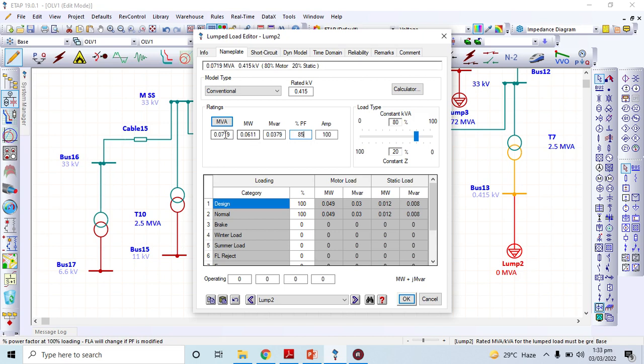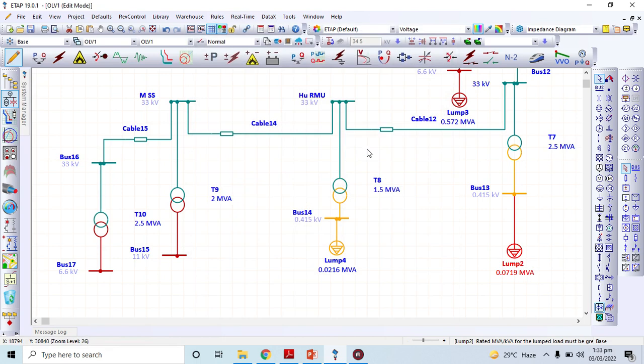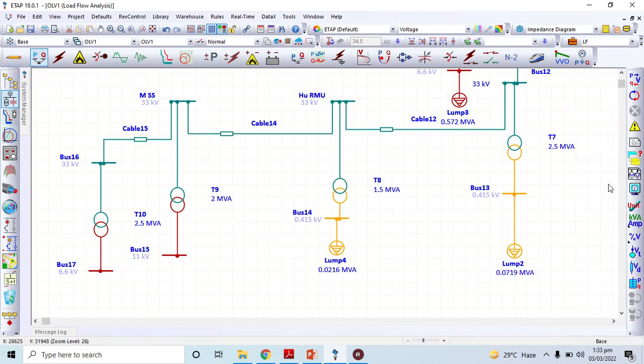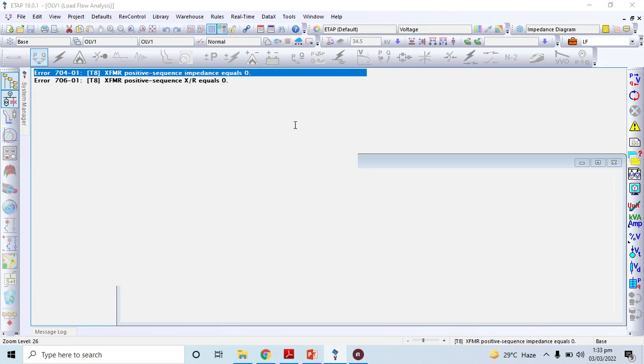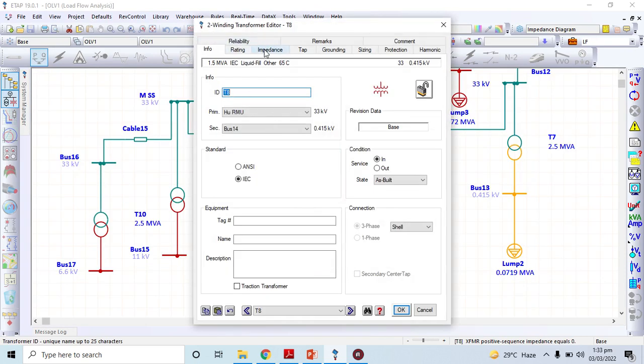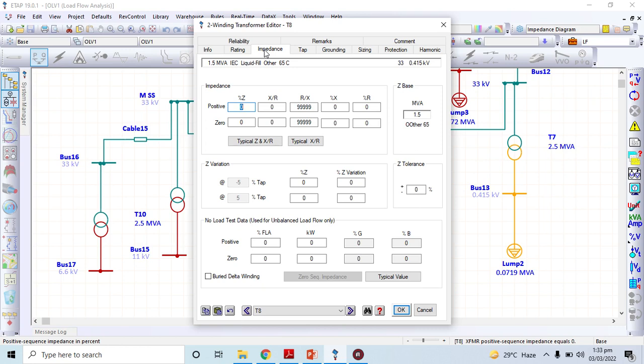The MVA active power values were auto-calculated. This current lump load is 80% motor load, so it represents some sort of combined small industry. Now I go to the load flow analysis. There are some transformers whose impedances I have to give the standard value. I told you earlier — if you have the datasheet of the transformer, you must use the percentage impedance or voltage drop as per the datasheet.